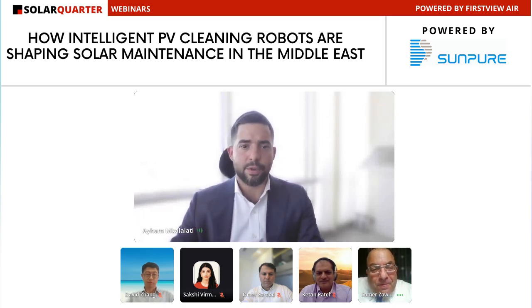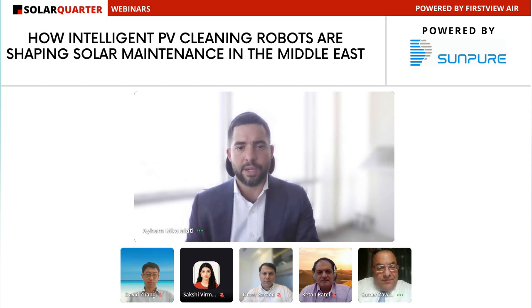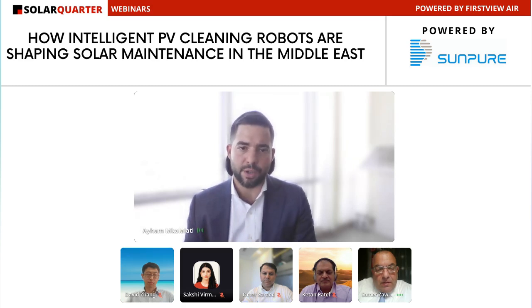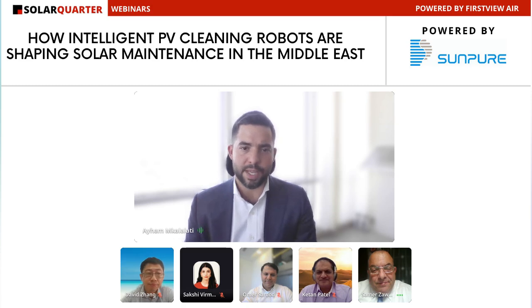Over to you. Yeah, it depends, it's either once per day depending on the plant, or once every week. But the brush material is quite important to consider. Some brushes are more abrasive than others, so it's really important to do trials with the robotic cleaning manufacturer to see what it does to the coatings on the module, since that coating is going to erode over time. This is a fact we have to live with. It's just a matter of how much it affects performance, and we do accelerated testing in third-party labs to verify that. So we've done accelerated tests on many of our projects.